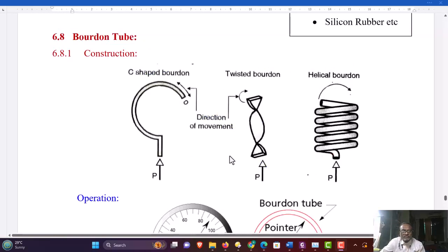Another primary transducer used for measurement of pressure is a Bourdon tube. A Bourdon tube is a tube of C-shaped English character. So as shown in the figure, this is a tube. Whenever we apply pressure to this tube, the freely moving end will move and the displacement of this end will decide how much pressure is applied to the pressure port. Figure 2 indicates the twisted Bourdon tube. In this case, whenever pressure is applied the tube is untwisted, and the remote end of the tube gets untwisted and the displacement of this end can be measured by using a displacement sensor.